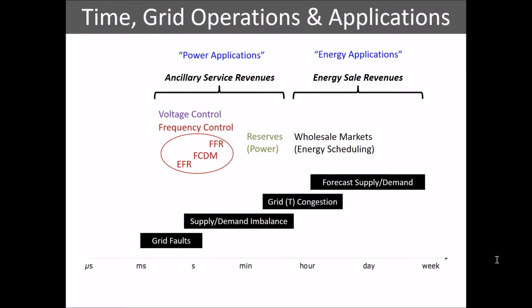Batteries in particular are very fast reacting. So you've seen, and certainly here in the UK, that enhanced frequency response has been quite good for battery providers, because batteries can go to their full output in milliseconds, so very quick responding. Battery storage can also play potentially into things like reserves, into slightly longer-term coverage of problems.